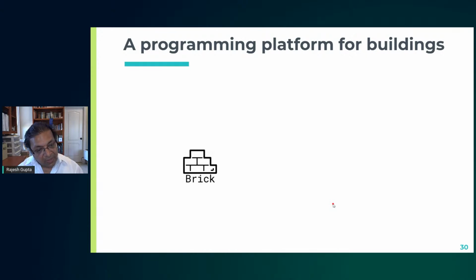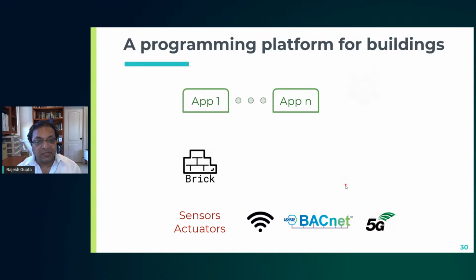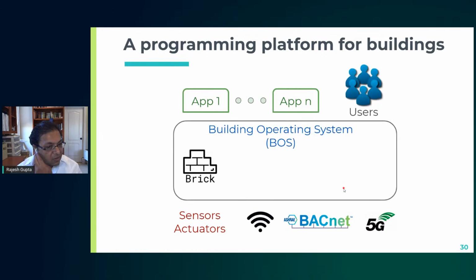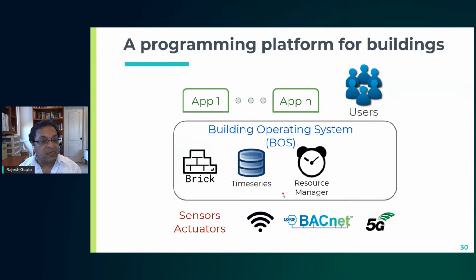So now you're beginning to see the infrastructure come up with the Brick server. It's not everything. It's the start of a much bigger programming platform that is needed. But Brick gives you the first portability, the first systematic way of organizing building information systems in a way in which programmed access can take place. You have sensors and actuators on top of that, and you have your typical sandwich of the operating system. Now, building operating systems have started coming up. Multiples have been built. You also need historical data. You also need a resource manager. You also need cron tabs. You also need timed operations. And of course, you do need control systems so that nothing bad happens.